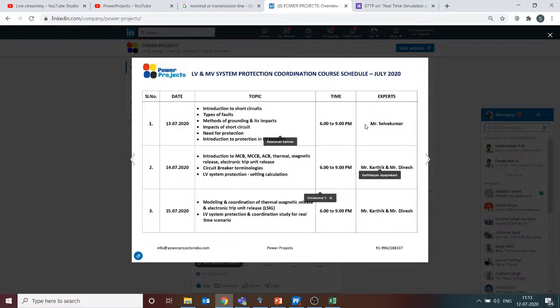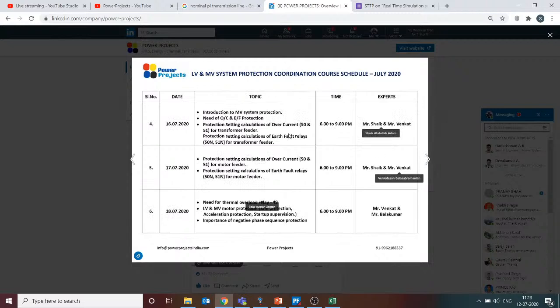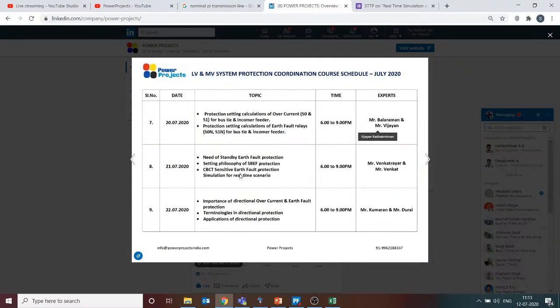And we are also covering the medium voltage. We are covering 50, 51, that is overcurrent protection, earth fault protection, instantaneous overcurrent, and 51 IDMT overcurrent, 50 instantaneous overcurrent, 51N, 50N. Including 67N for all the equipment we are covering, like transformers, motors, cables, feeders, bus bars, incomers, for a radial system, meshed systems. In addition to that, a little bit we are covering on the CBCT also for sensitive earth fault protection. And we are also covering different topologies and case studies, and we have a session on the CT VT sizing also. And that's about the question.